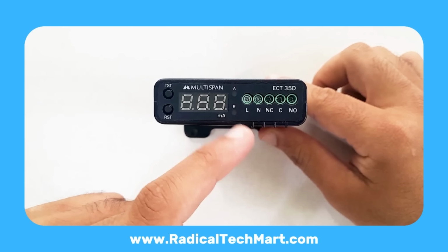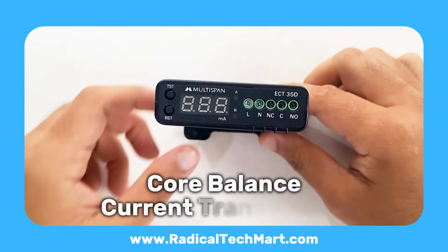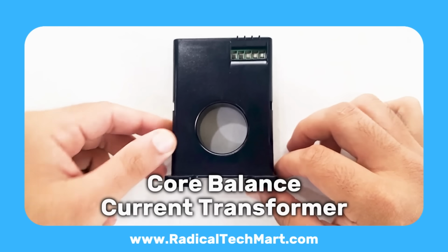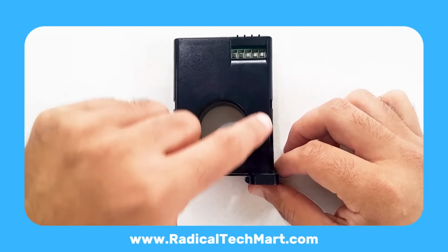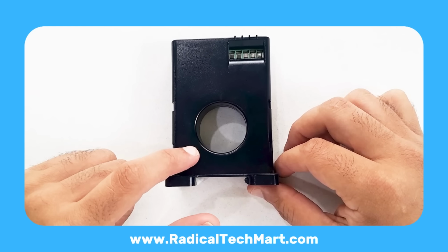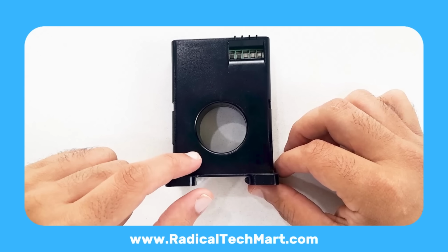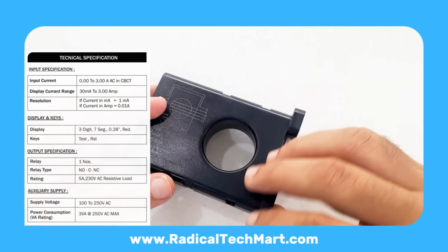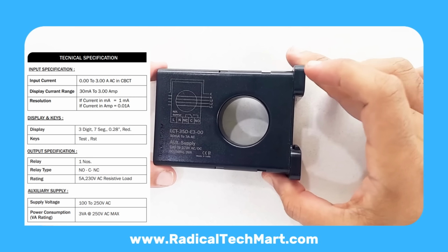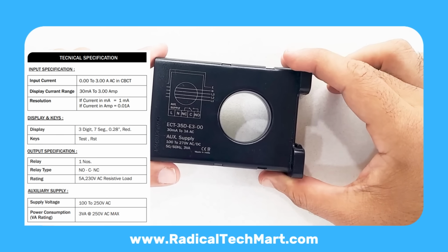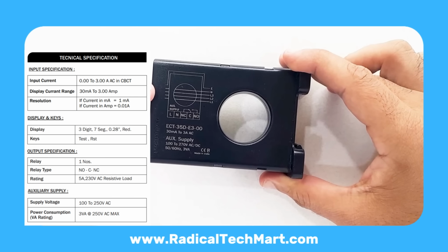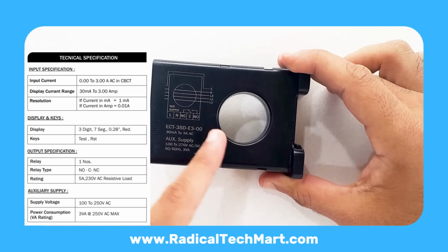You'll also notice a circular marking on the unit. That's actually the CBCT, core balance current transformer, symbol. In this model, the CBCT is built in, so you don't need an external one. Now, let's talk about its parameters and specifications. On the side, you'll find the wiring diagram. Your three-phase lines and neutral must pass through this inbuilt CT loop.